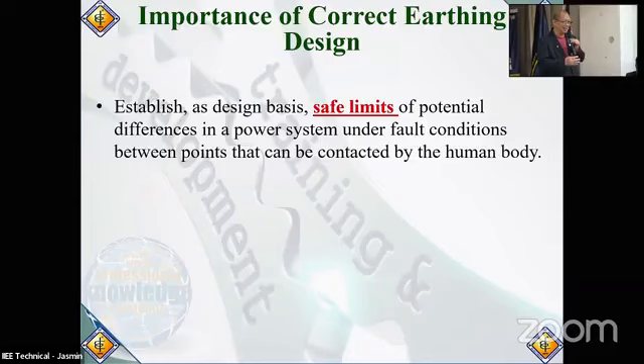Maybe a lot of people will ask where the two converge or how they relate to each other. PEC focuses on how we execute the earthing system, bonding, where it's going to be connected and how. But IEEE 80 is the calculational component where we have to determine the performance of the earthing system during fault conditions. Kasi alam natin, during fault conditions, in theory your earth is at 0 volts, but in a faulted condition that 0 volt is not 0. So what happens during faulted conditions, how does the earthing system perform? That's IEEE 80. So they complement each other.